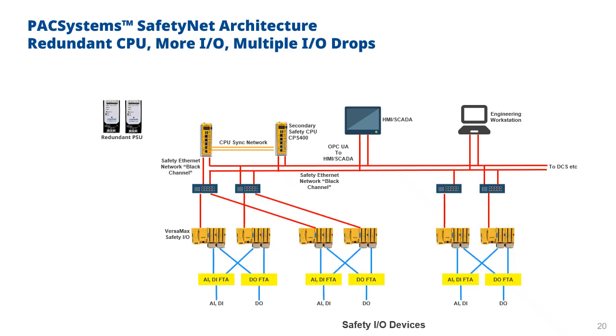So here we see the same as before, but now using those switches, we can link with additional network cabling down to additional I/O drops. And by having additional switches, we can also have a distributed system all running off that safety Ethernet network, black channel network, and we can distribute pretty much as far as we like. We are using EGD, which is non-routable, but potentially with a combination of the correct switches and fiber networks, these could be several hundred meters or even kilometers apart from each other.